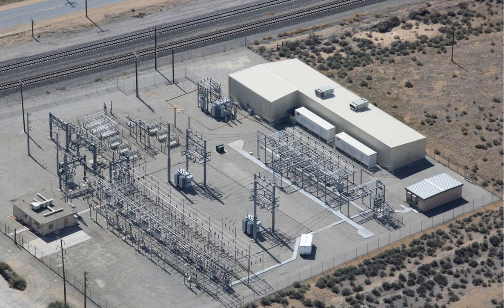The history of seismic activity in Kern County, including damage to substation structures, created some challenging system design requirements, such as having the populated battery racks designed and tested to meet IEEE 693-2005 recommended practice for seismic design of substations. Since commissioning in 2014, the area has experienced not only seismic activity, but also flash floods and subsequent mudslides. One key lesson learned is the importance of subscale testing by the electric utility prior to full system deployment so that the safety and operational controls and features could be fully evaluated.